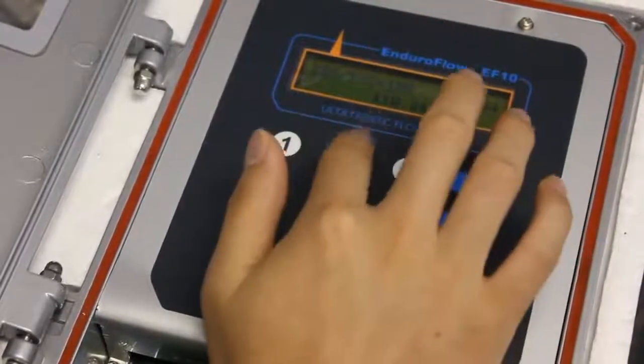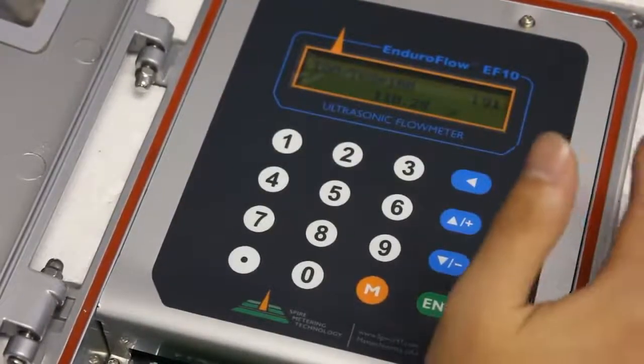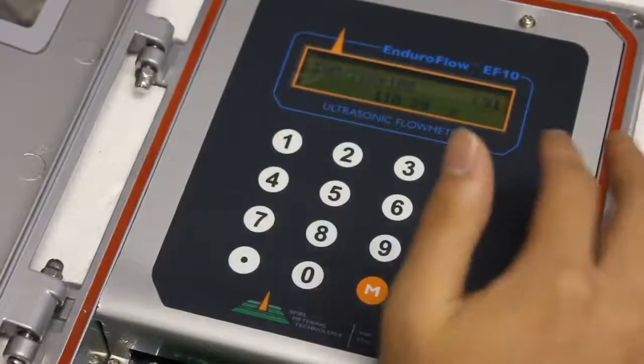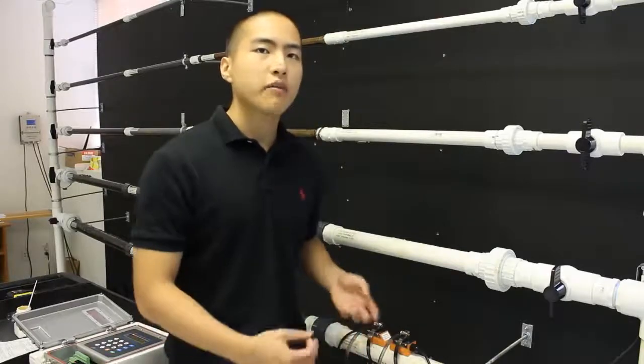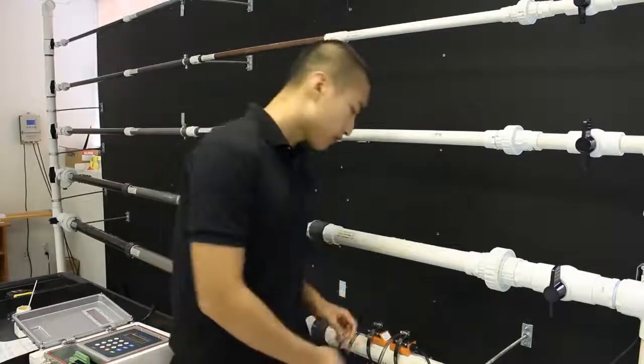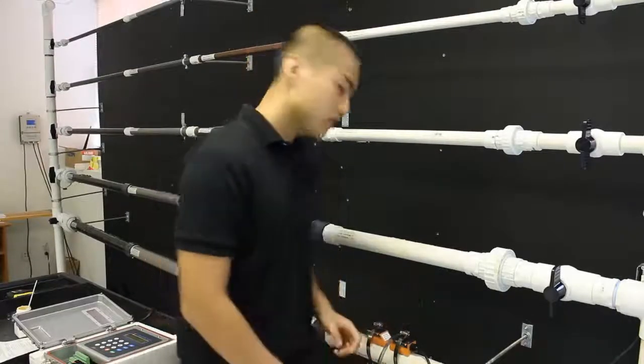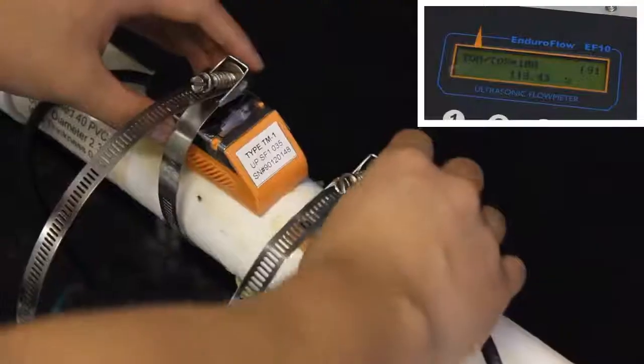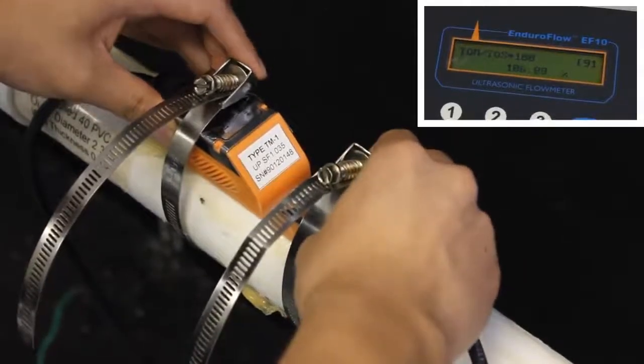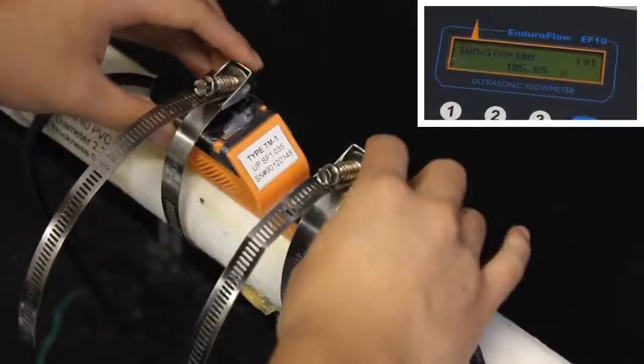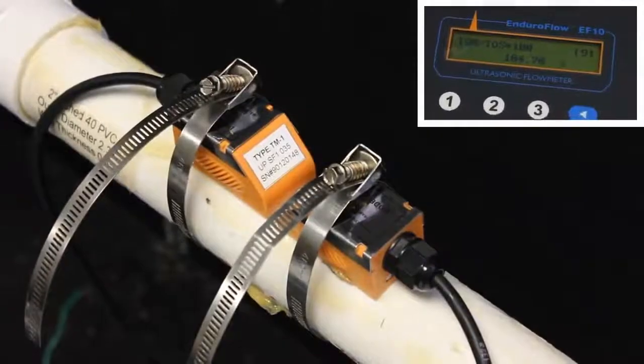At 118 it's way too high, which means we need to adjust the spacing between our transducers to change the value here. Because the value we had on menu 91 was too high, what that means is we need to move our transducers closer to each other. Now if your value is too low, then that means your transducers are too close and you need to move them farther apart. So here we're just going to move them a little closer. Basically you just keep adjusting them until it's as close to 100 as possible.